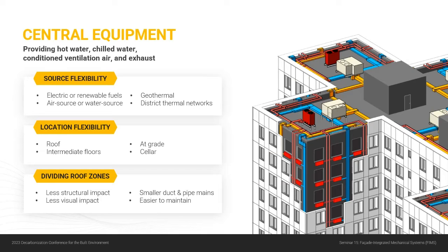We'll start by talking about the central equipment. It is providing hot water, chilled water, conditioned ventilation air, and exhaust that gets distributed throughout the building. An important thing to note is that it's very flexible in terms of the type of central equipment we use. So it's flexible in terms of the source. This can be conventional electric heat pumps, or it could be something driven by natural gas, renewable natural gas, something like that. It can be air source or water source heat pumps, which means it can connect into a geothermal network or a district thermal network, or you don't even need heat pumps if you have a district thermal network giving you hot and chilled water.